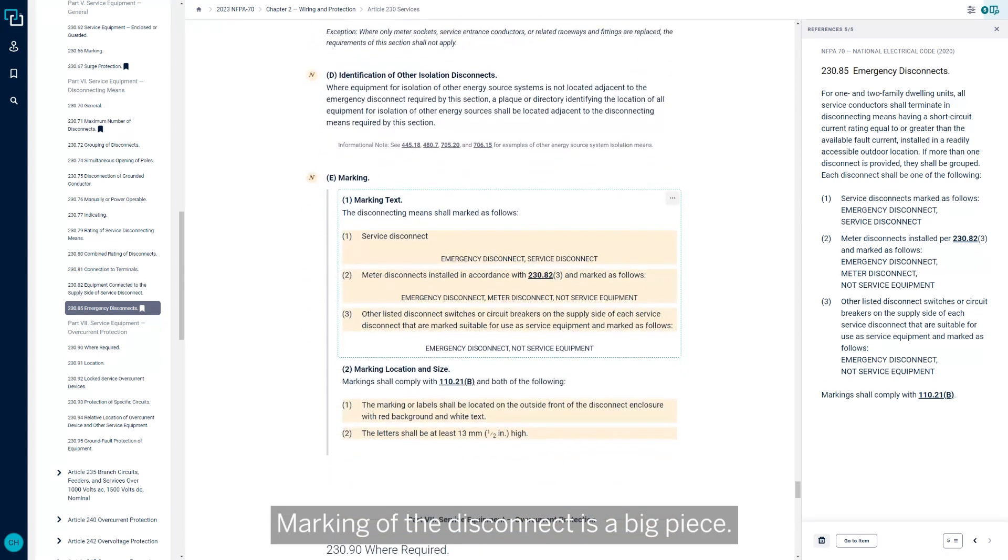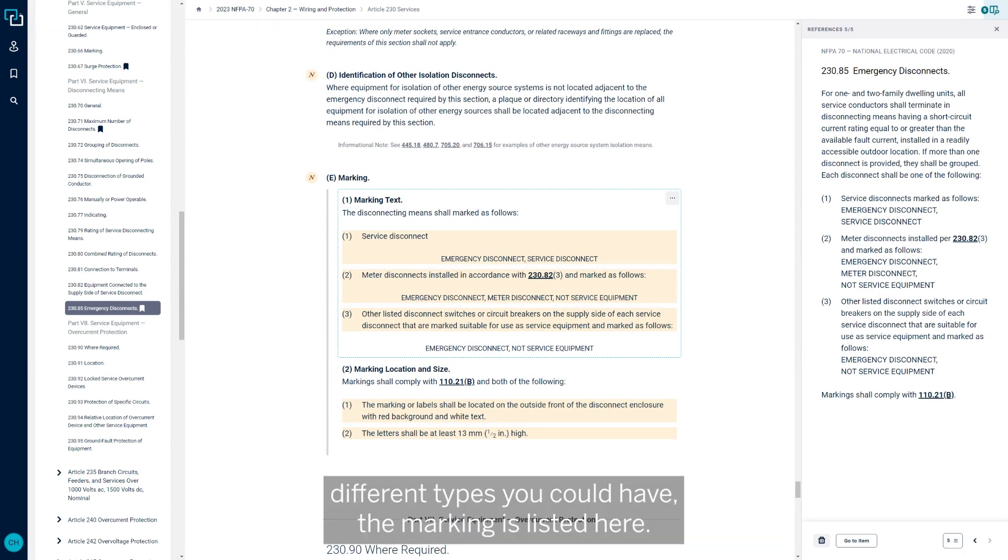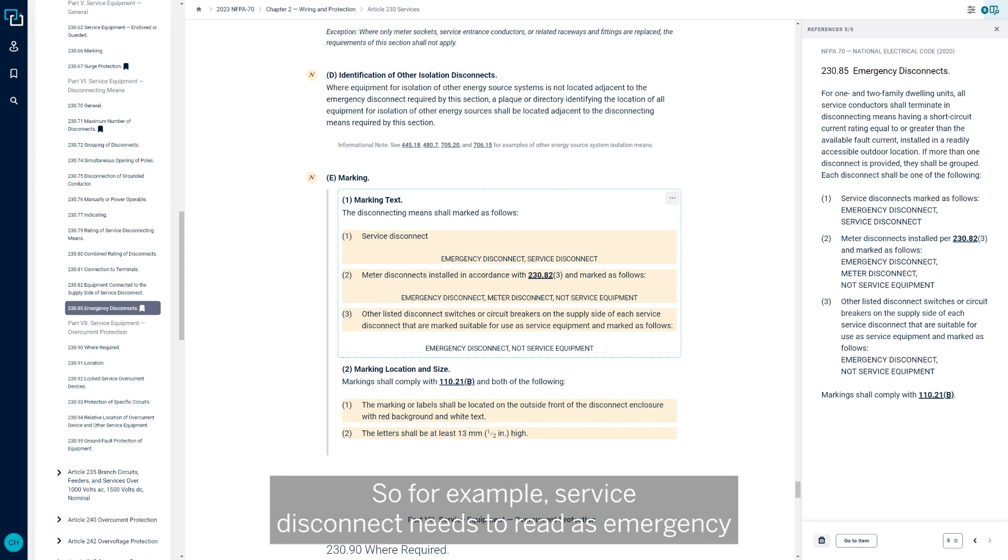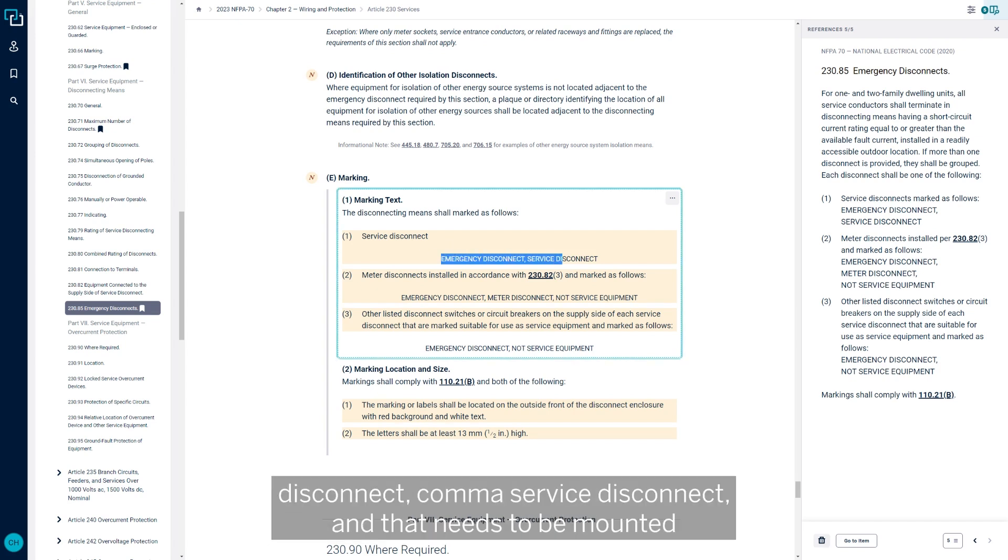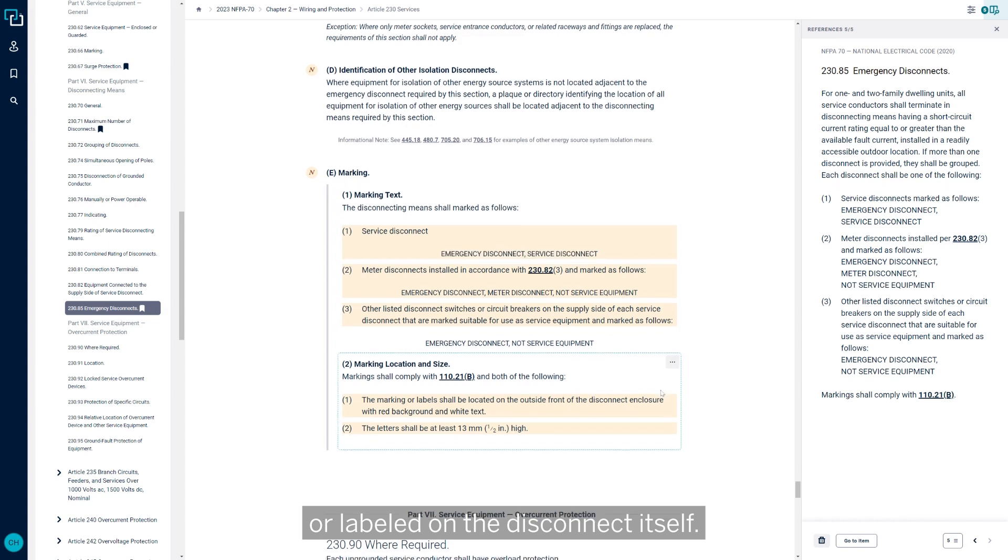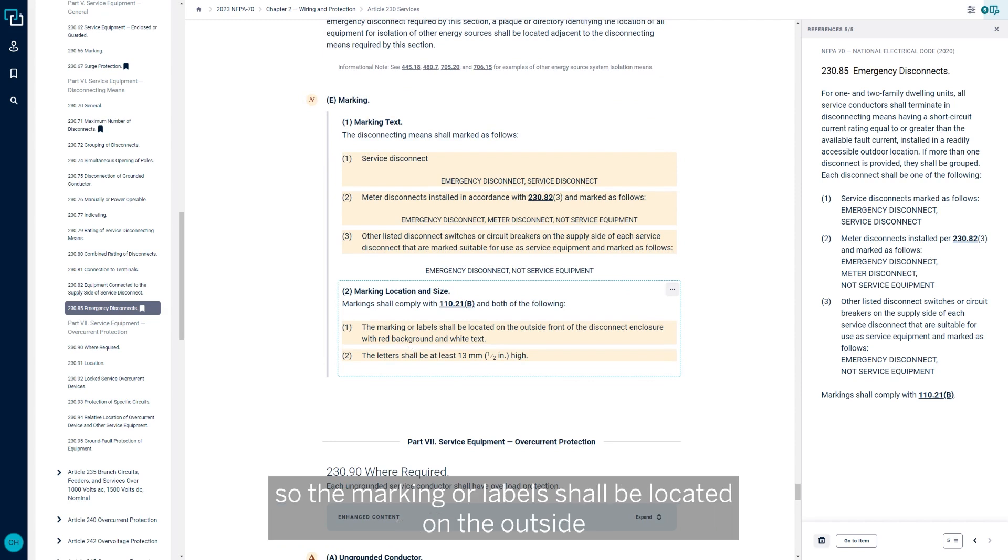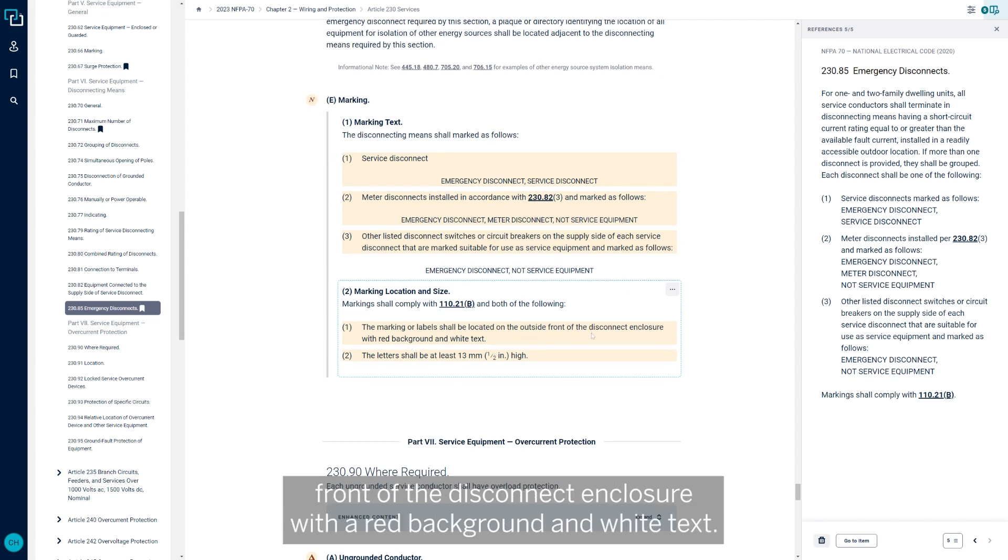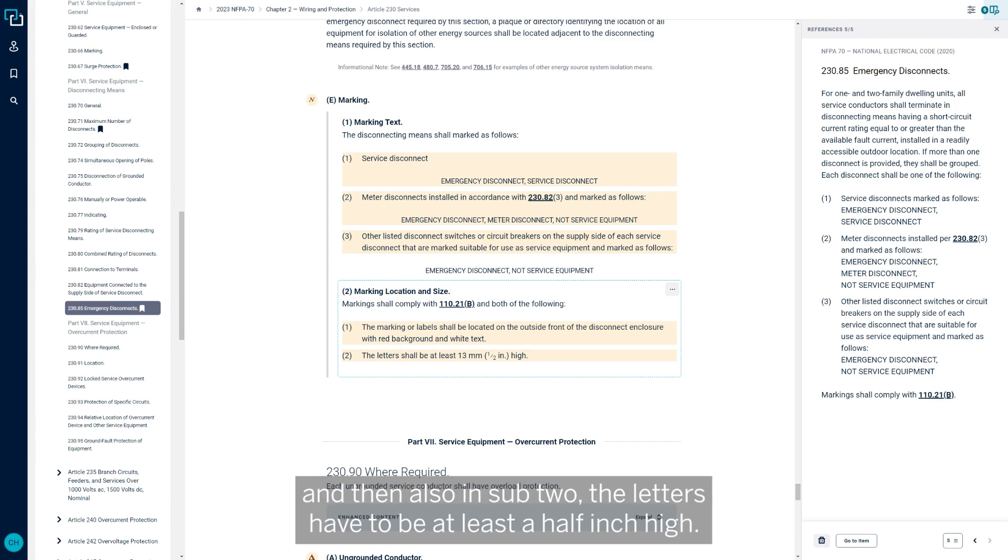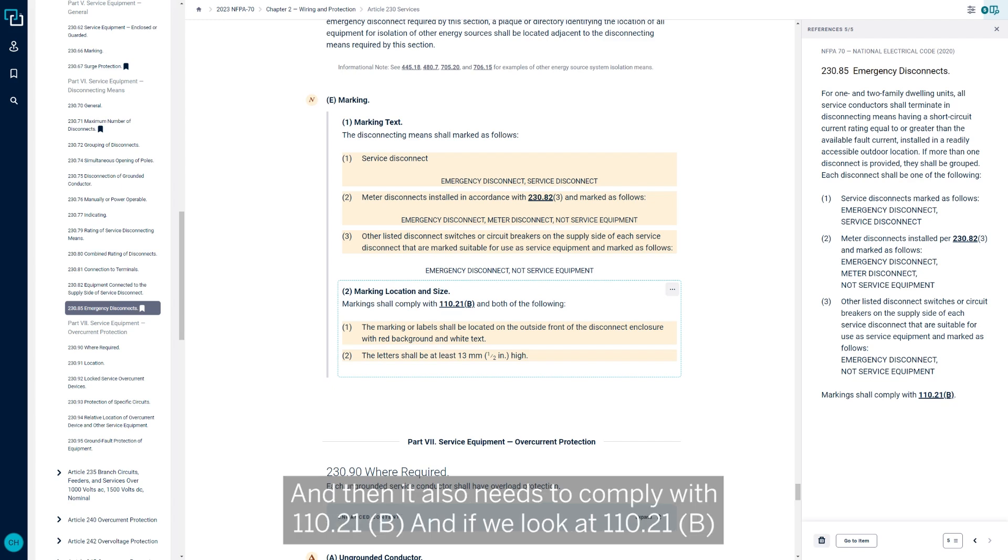Marking of the disconnect is a big piece. The disconnect itself, depending on the three different types you could have, the marking is listed here what it needs to say. For example, service disconnect needs to read as emergency disconnect, service disconnect, and that needs to be mounted or labeled on the disconnect itself. The marking location goes into that a little more in size. The marking or labels shall be located on the outside front of the disconnect enclosure with a red background and white text. So it's pretty clear it needs to be red background white text. And then also the letters have to be at least a half inch high. So there's some criteria here specific to how it has to be marked.